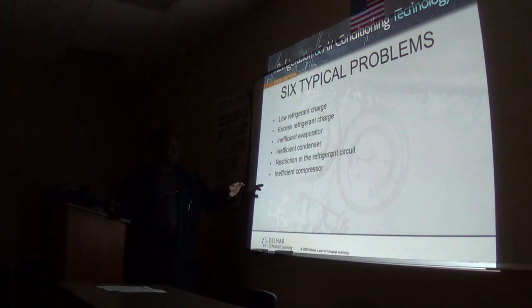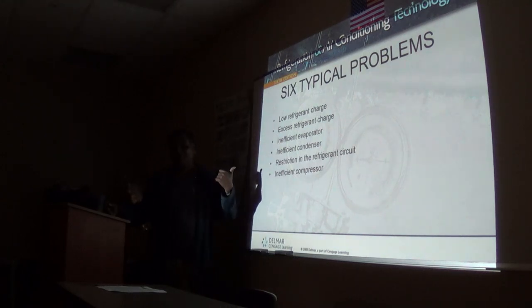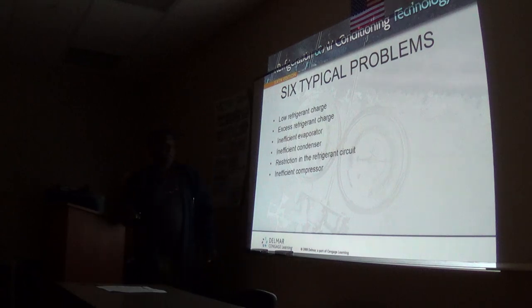Yeah. So, like I say, a restriction on this side will tell you, hey, I'm overcharged. But on this side, it's going to tell you, hey, I'm undercharged. Now you've got to make up your mind which one you want to go by. Typically, it depends on your metering device, and they say with the TXV to just charge on the high side. Charge going by your high side, and leave the low side alone. Don't pay attention to it.